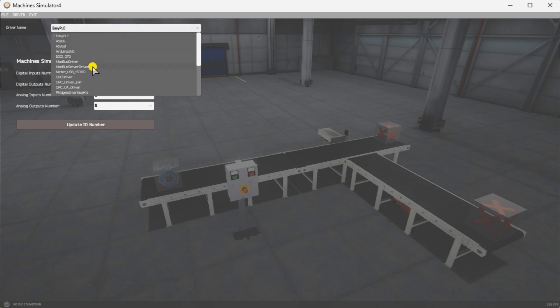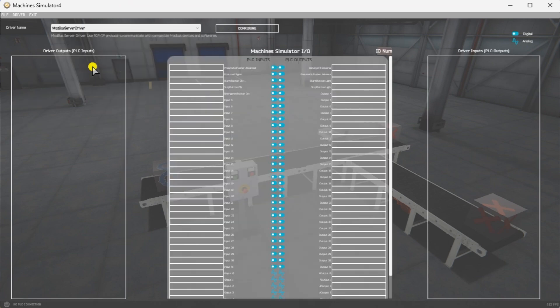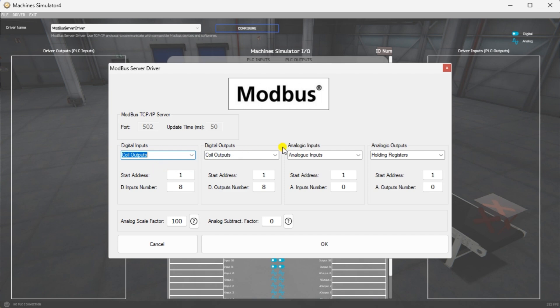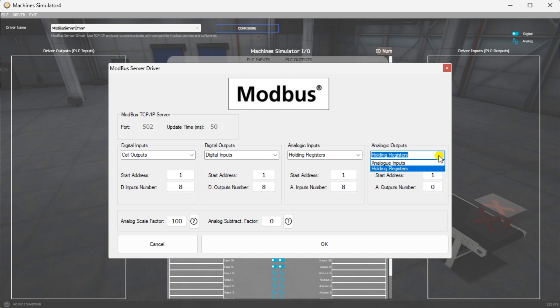Select Modbus server driver. The Modbus server driver uses TCP/IP protocol on Ethernet to communicate with the other Modbus devices and software. Select the Configure button. We will now assign the machine simulator to the four different Modbus memory areas. The PLC's coil outputs will be the MS digital inputs. The PLC digital inputs will be the MS digital outputs. Modbus PLC holding registers will be used for the analog inputs, and the PLC analog input registers will be the MS's analog outputs. Analog scaling and subtraction factors are used in the machine simulator to represent negative numbers, since Modbus analog is strictly a 16-bit word. Select OK.